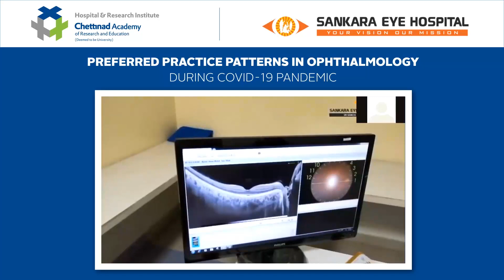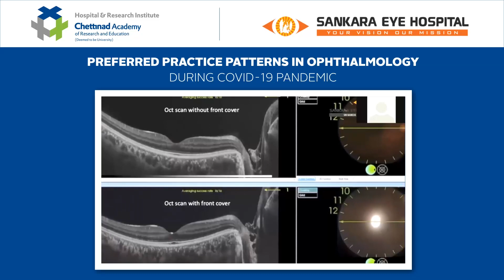Take an adequate length of the cling wrap to cover the front surface, including the lens and the sensors of the machine, attaching it to the side walls. The entire process of covering hardly takes 5 minutes to complete. Make sure that there are no folds in front of the lens. The covering can be easily cleaned between patients and changed at the end of the day. As you can see, the scan quality is not affected. This picture shows a comparison of image quality obtained in an undilated patient without and with the front cover.